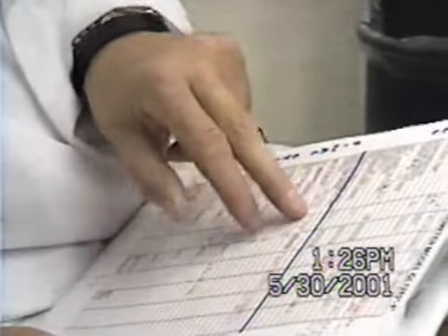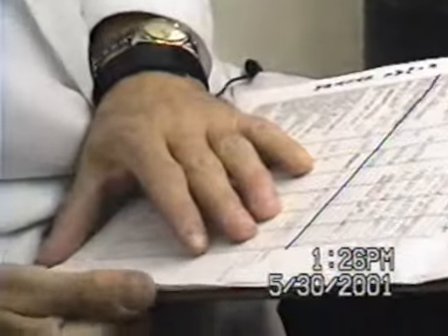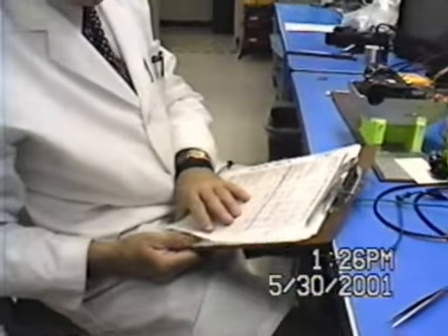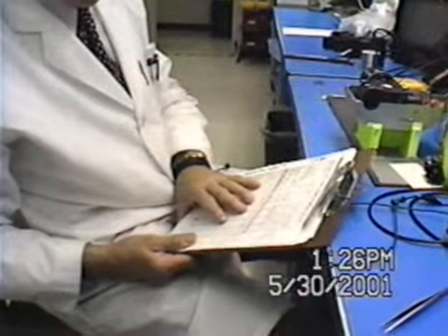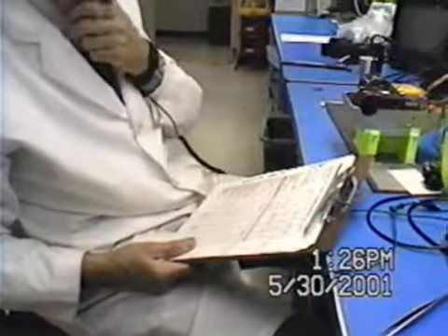If you calculate the normalized radiance for the display temperature and the actual temperature, the ratio of the radiances is 0.33. So the new feedback resistor should be 10 mega ohm times 0.333, which would be 3.33 mega ohm.